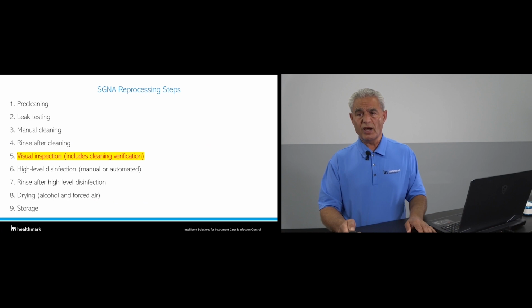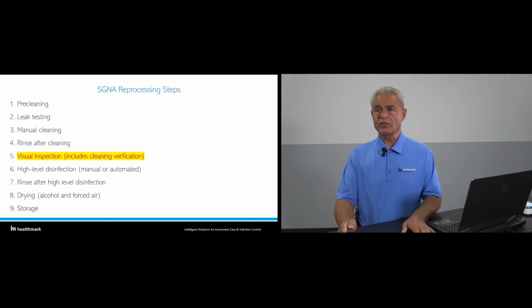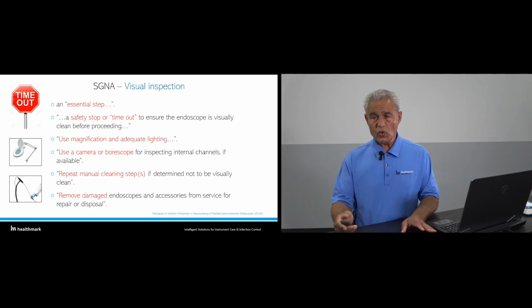Those are some of the reprocessing steps. It says visual inspection is an essential step, a safety stop or timeout, to ensure the endoscope is visually clean before processing, using magnification and adequate lighting. Use a camera or borescope for inspecting internal channels if available. If you find debris, you need to repeat the manual cleaning and determine whether it's visibly clean. Part of this process is to remove damaged endoscopes and accessories from service for repair and disposal.